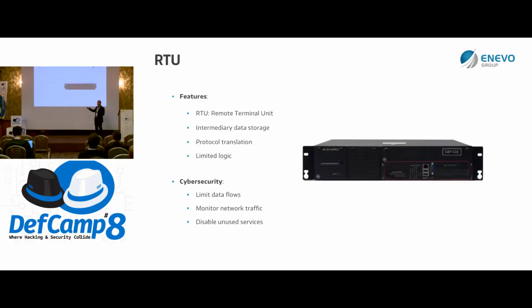All those PLCs send data to a remote telemetry unit via industrial communication protocols. So it has an intermediary data storage, a real-time database. It does protocol translation, because PLCs on different zones of the infrastructure can talk on different protocols, and you need to unify those into a common language. This is where the RTU comes in. Usually it can talk multiple industrial control protocols. Again, not very much cybersecurity you can do on them.